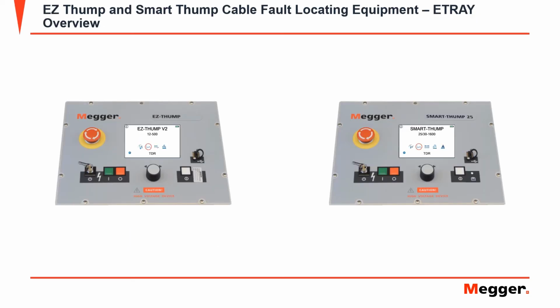The EZ Thump and the SmartThump are both equipped with a TDR feature, which is a reference trace. It does so by using a low voltage pulse. The locate feature is to help locate the fault. This is accomplished by overlaying an arc reflection over the TDR.